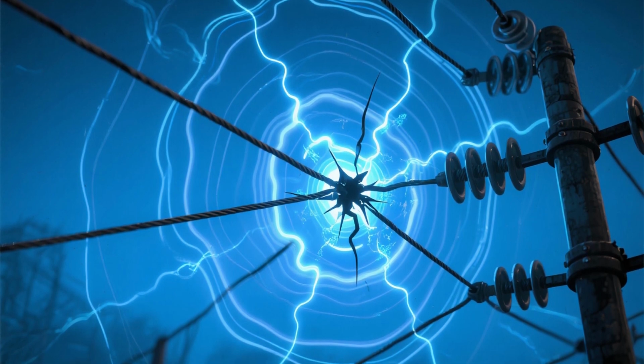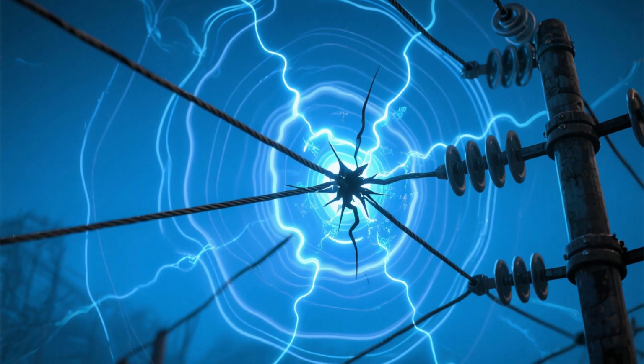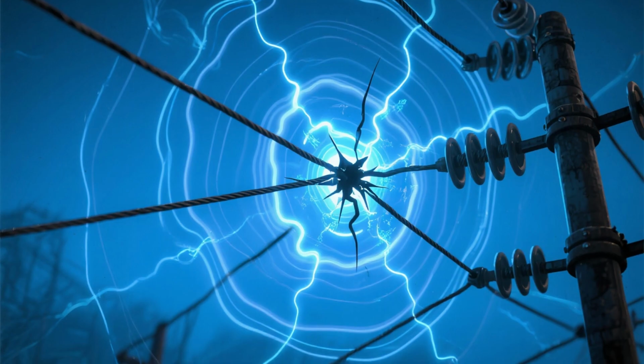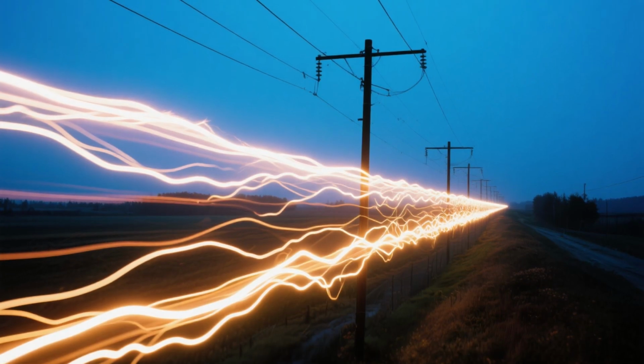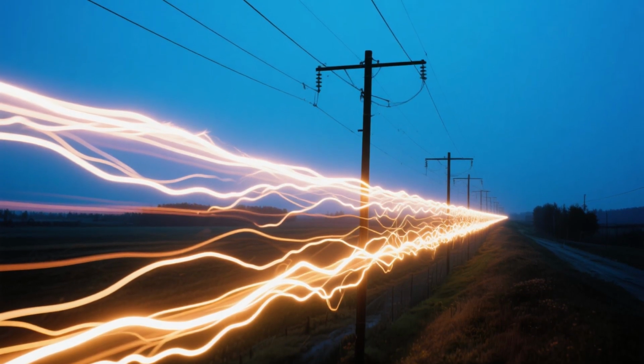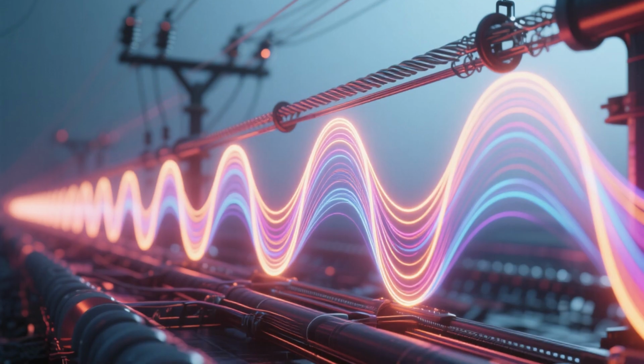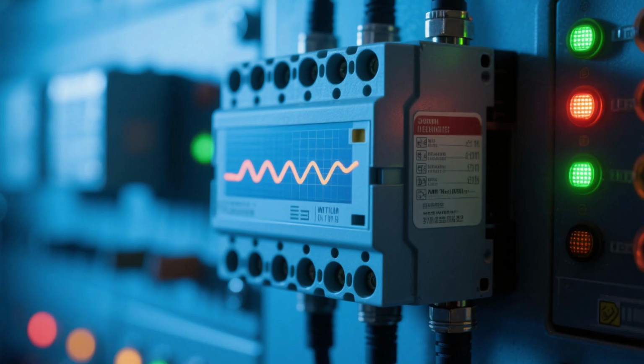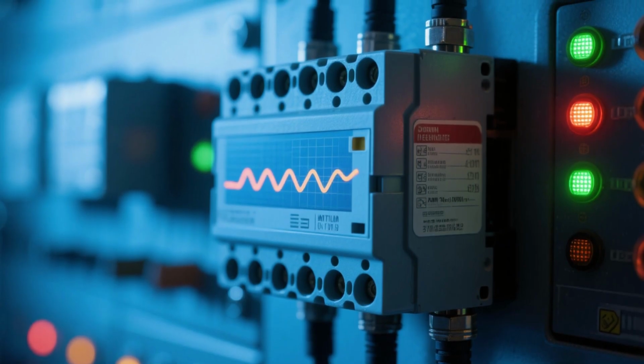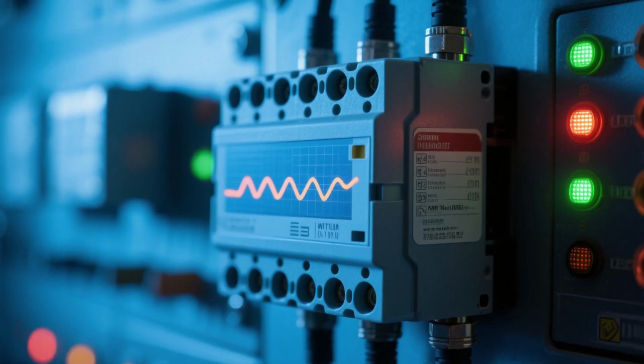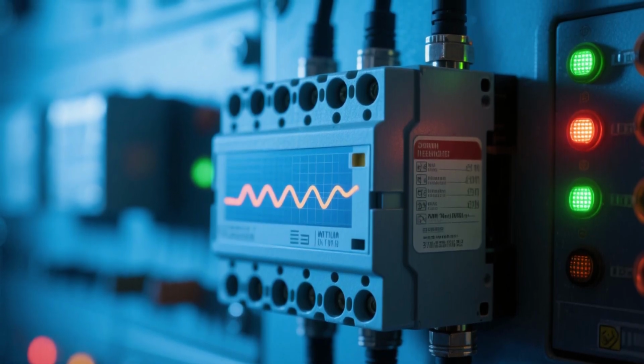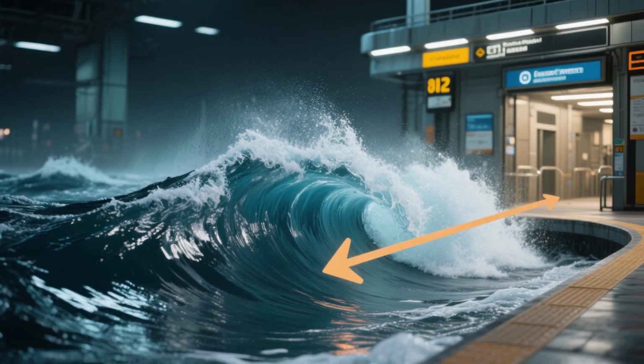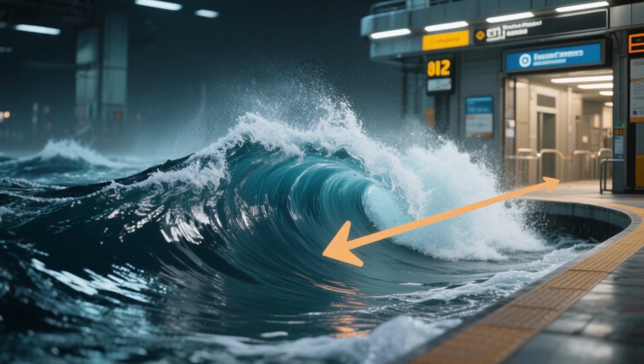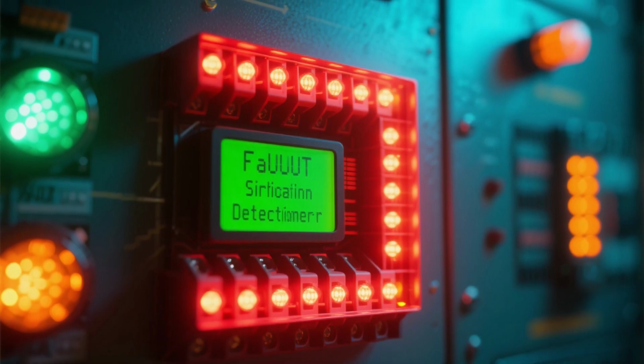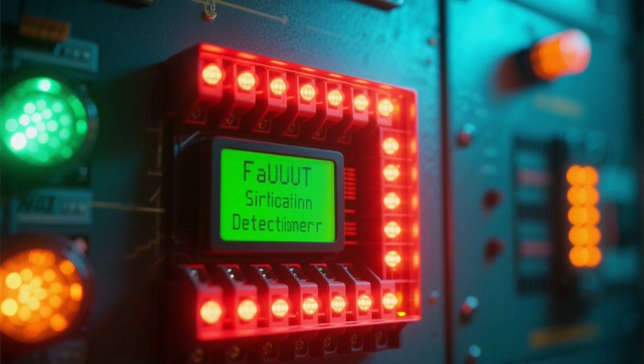But instead of water ripples, it generates high-frequency electromagnetic waves of voltage and current that travel along the line in both directions at nearly the speed of light. These are the traveling waves. Detectors or relays installed at each terminal of the transmission line are constantly monitoring for these waves. When a fault occurs, the wavefront reaches the nearest terminal first. The relay at that terminal detects this sudden change and can almost instantly recognize it as a fault signature.